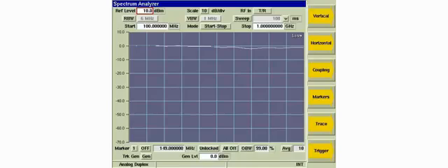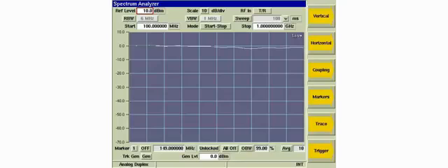This trace represents the loss of the reference cable from 100 MHz to 1 GHz. This trace will be used as the reference in our measurement, so we need to set it as the reference trace.